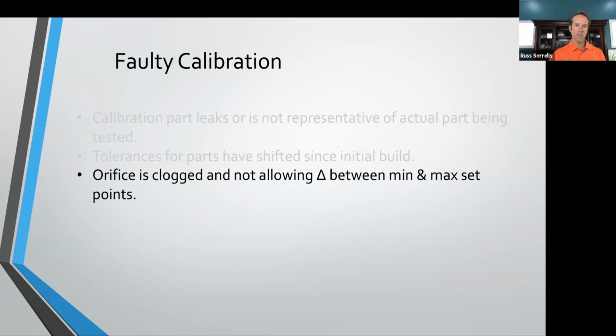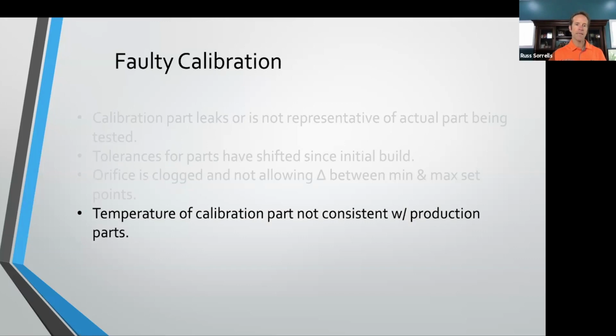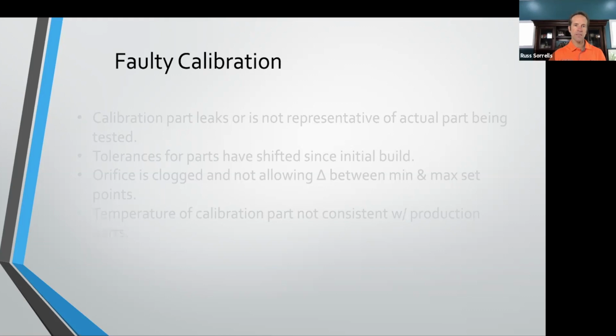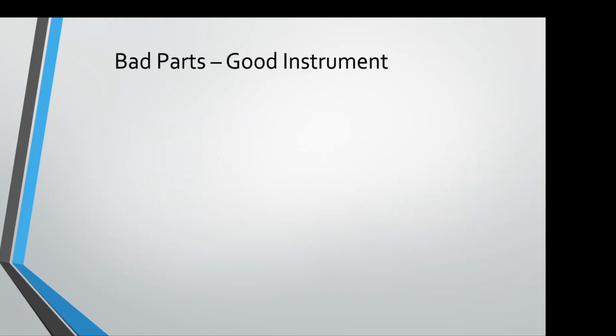For those issues, the leak standard can become clogged, and there's no difference between the no leak part and the no leak part plus the leak standard. That is obviously a problem. The temperature of the calibrated part not being consistent with the temperature of the parts that you are testing on a day-to-day basis can also cause issues with calibration. Yeah, porosity is another one.